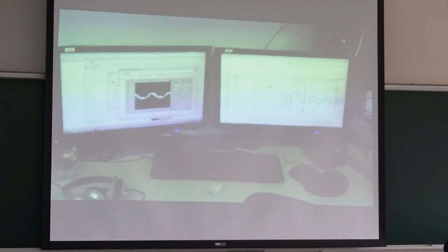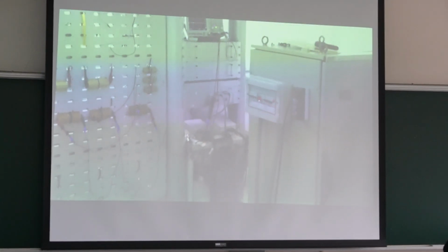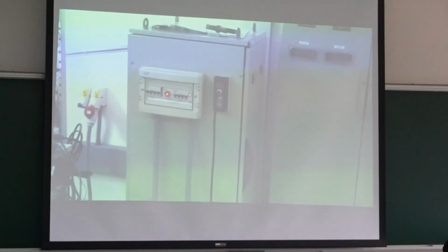Okay, so this is a new device we call the silicon carbide AC switch. And then we will see a demo of a matrix converter. This is a real matrix converter, and you can see the scope to watch the voltage and the current. So this is a new device. It is a smaller size than a traditional inverter. So compare the large one and the small one.